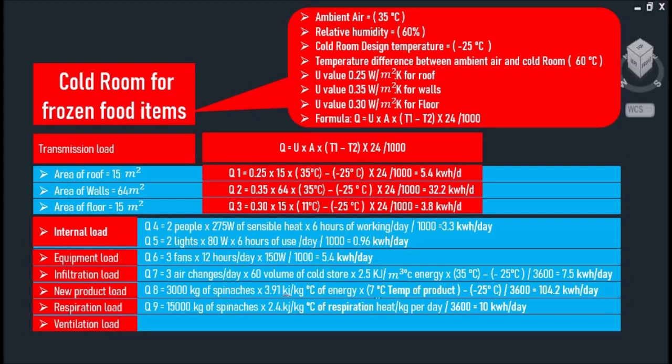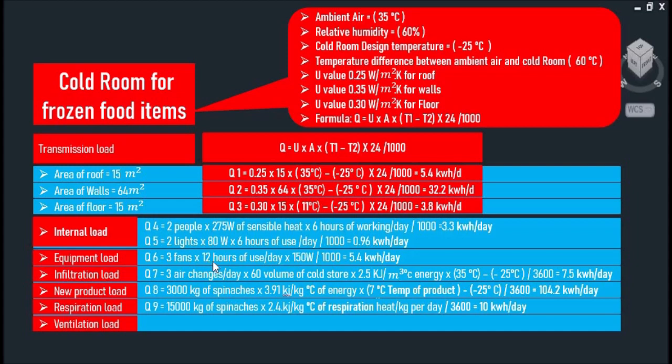Two lights multiplied by watts multiplied by hours of use per day divided by 1000, that comes to 0.96 kWh per day. And the third one is equipment load with three fans multiplied by hours of use per day multiplied by watt and divided by 1000, that comes to 5.4 kWh per day. And you can also include the defrost element.